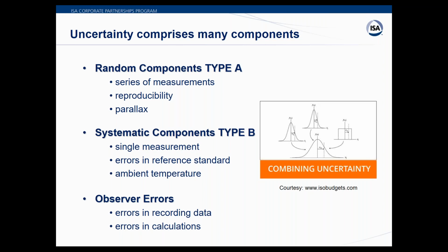But notice the list for systematic. We're talking about a single measurement. When you do an As-found test, you're making single measurements. You're maybe going up and down, but it's just one cycle. The standard you're using is what it is that day, and the temperature is pretty consistent. You're only out there for less than an hour, or maybe something more complicated, a couple of hours, but the temperature is pretty consistent over that test period. And finally, if you are recording things, people can fat-finger things, or you can't read the writing, or if they're having to make a calculation, they could make a mistake.